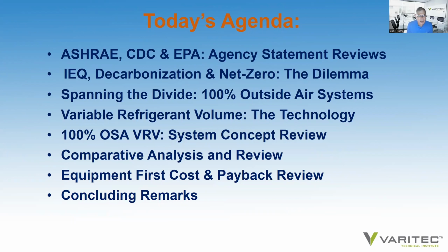Today we're going to look at ASHRAE, the CDC, and the EPA, and agency statements on how we improve indoor air quality and indoor environmental quality of buildings. We're going to look at IEQ, decarbonization, net zero, and the consequent dilemma. We're going to look at spanning the divide of that dilemma with a proposal for a 100% outside air system using variable refrigerant technology. We're going to explore variable refrigerant technology, a very quick overview of the system and why it achieves its efficiency levels. Then we're going to look at 100% outside air VRV, a system concept review. And then, in line with the article that I mentioned earlier, we're going to do a comparative evaluation.